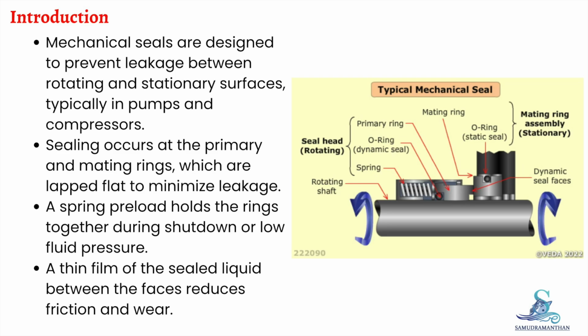A spring preload holds the rings together, maintaining the seal during shutdown or when fluid pressure is low. A thin film of the sealed liquid is maintained between the sealing faces. This film is crucial because it reduces friction, minimizes wear, and ensures long-lasting performance.